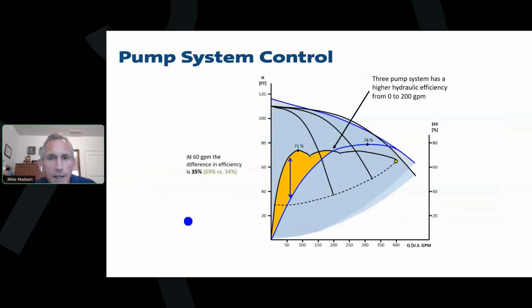Okay. Great question. So something else we can do with the packages, this is a curve that shows a big pump, or a package that in this case has 3 pumps. The other thing we can do when you have a package is you can run a smaller pump to handle your part load conditions. And so we can see the big pump is very efficient. It's 78% efficient at design flow, but we know that we don't operate very often at that design flow. We spend a lot of time down here under part load conditions. And even though I have 3 smaller pumps that are a little less efficient, 72% in this case, when we are operating down here at these lower flows, which happens a lot, we're going to save additional energy. So that's another benefit of having a package, so that we can put multiple pumps and only operate what's needed instead of running one big pump as an example.